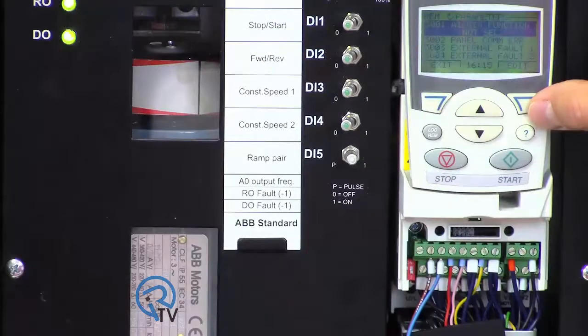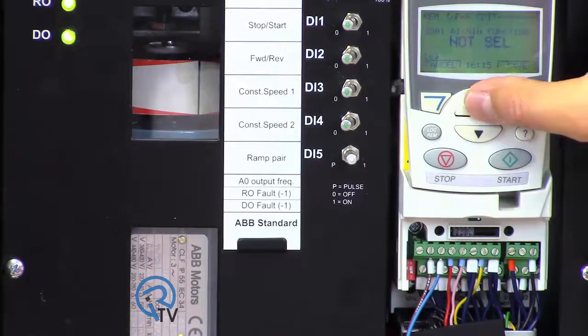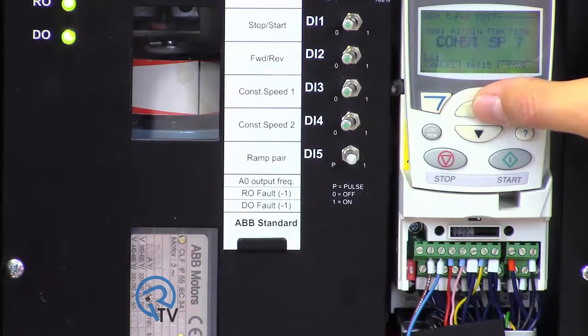We can set some protection in the drive in case we lose our sensor signal. Parameter 3001 can be set to default, constant speed 7 which is user-defined, or the last speed used.